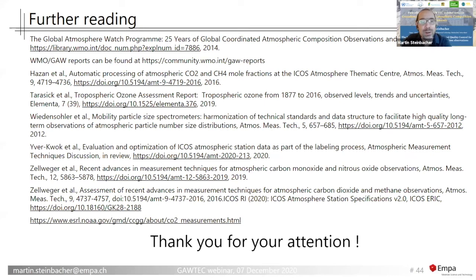Okay, well, we do that every couple of days. Finally, if you do that every day or every second or every third day, it doesn't change much, because once you do that so frequently, you do not want to do that manually. That means you need some valve, some calibration box that can do that automatically, or you can set a programmable box that can switch automatically between calibration gas and ambient air. And then it doesn't matter if you do that once a day or every second day. It is more a matter of the calibration gas that you need.